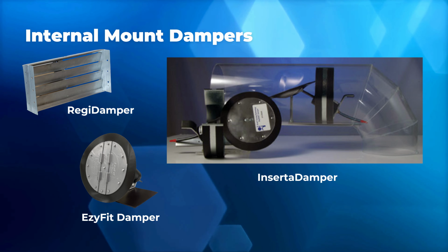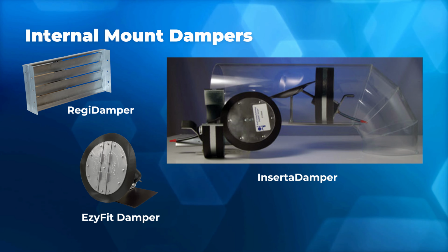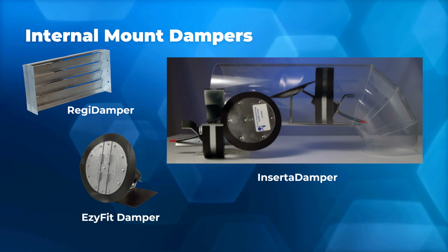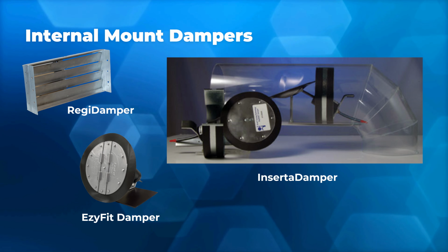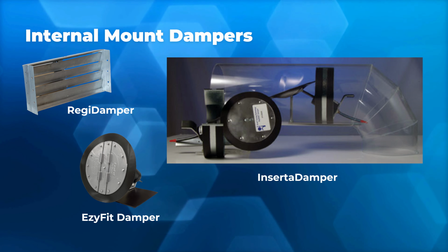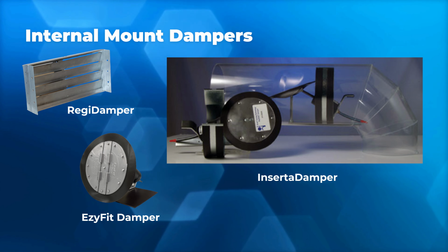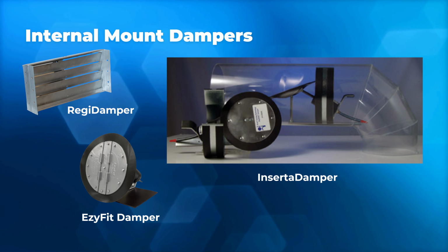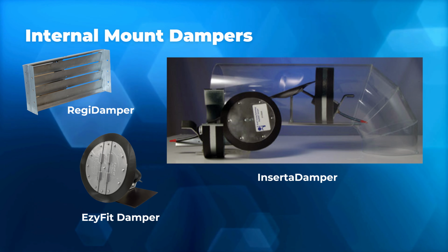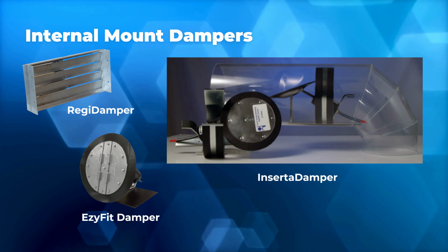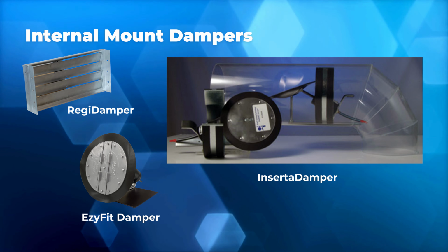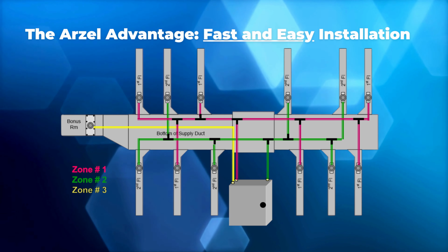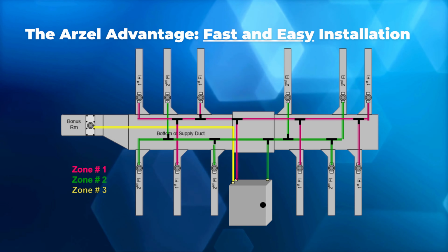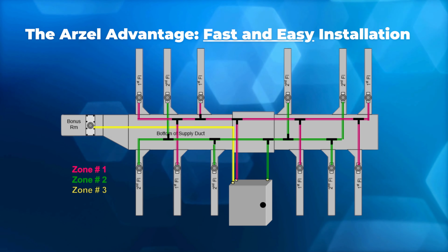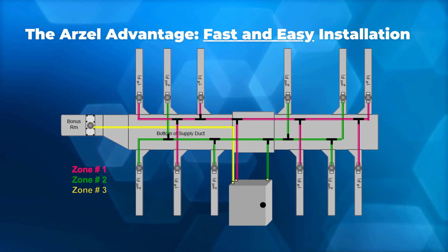One of the other things that some of the techs do to run the tubing itself when you're doing internal mounts is if you do ductwork cleaning, a lot of the guys will use their duct vacuum, and then they'll tie a plastic baggie on a string and suck that through their ductwork, and then essentially tie your tubing and pull it back through. So there's a lot of creative ways you can do it, but those are kind of the two top ones that most of the technicians are using out there to run the tubing itself. So this is kind of your basic layout for a 3-zone system. So each one of the colors there is going to represent a zone.